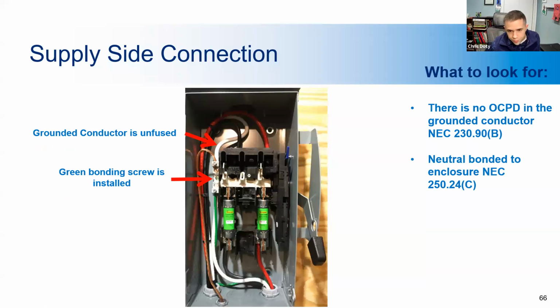Okay, so in light of the fact that the supply side conductors are similar to a second set of service entrance conductors, in that they're unprotected from utility side current potentials, the disconnect that serves as a supply side connection has to be bonded similarly to a service panel, where the neutral and ground are bonded together. You can see that in the photo here. This green screw is used to bond the bare ground wire and the neutral, and also this green ground wire. So that was done correctly in this situation, and that creates the bond between the neutral and the ground that allows overcurrent protection devices to operate properly, and it also grounds the enclosure.